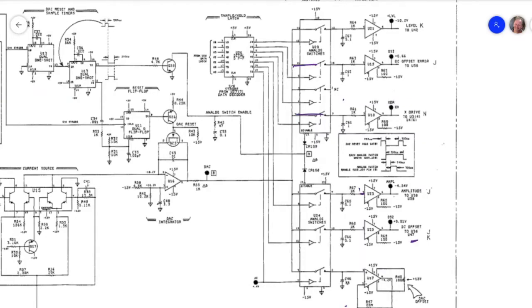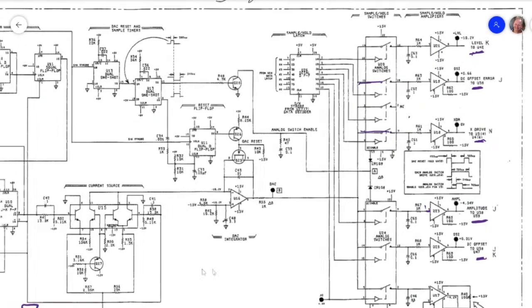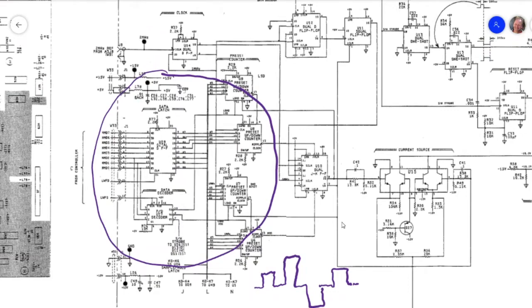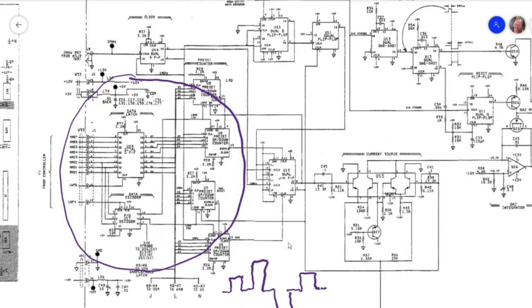Okay, so let's take a look at this circuit right here. There's a number of different voltages that we need to do digital analog conversions to, and they're right here. They're DC offset, the amplitude, the X drive, the DC offset error, and the level. I think level is used when it's doing its calibration, but amplitude is the one that we're seeing is messed up. And so if we come over to this part of the circuit that I've got circled right here, that's the D to A converter and the interface to the computer, right?